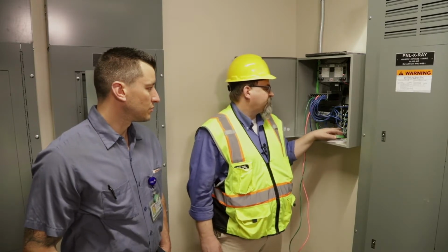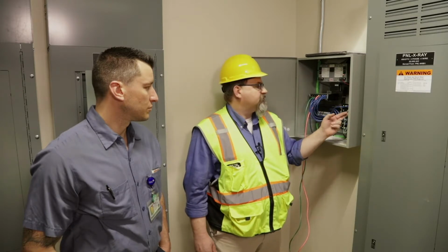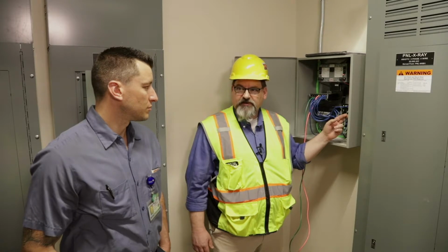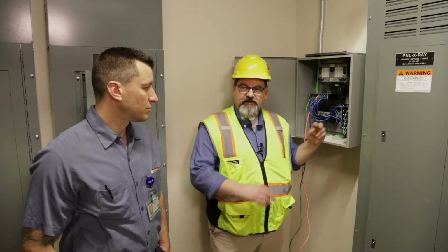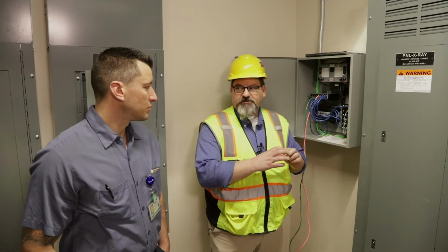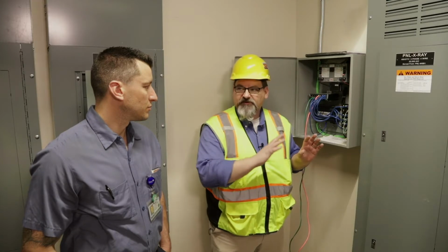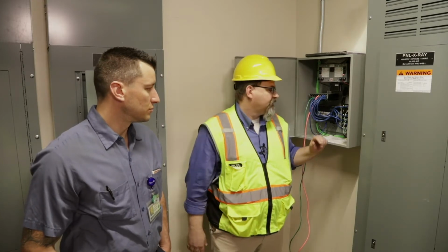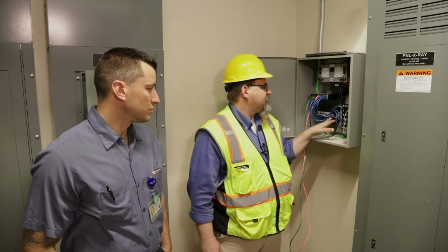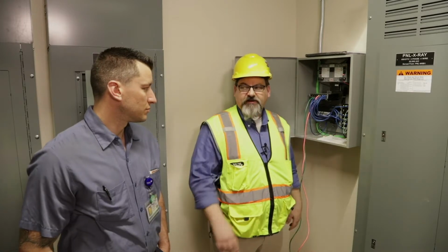All right, so this is floor 1, 2, 3, 4, and this is floor 6. This goes MSTP style, twisted pair. 2 wires essentially are communicating, 1 wire for a reference. At the end of this chain of wires, there's a resistor that terminates it, so we don't have a mismatch on the waveforms to the different wires, right? It's all one steady ringing sound, right? This interfaces with those devices, and then we have a web page that's served up from this, and I'll show you that web page.